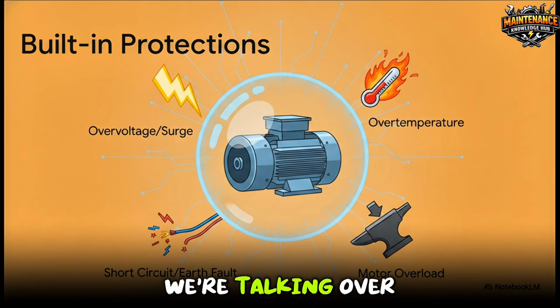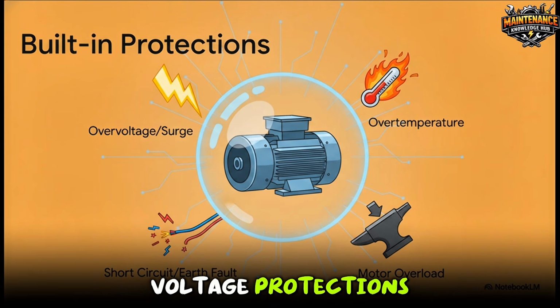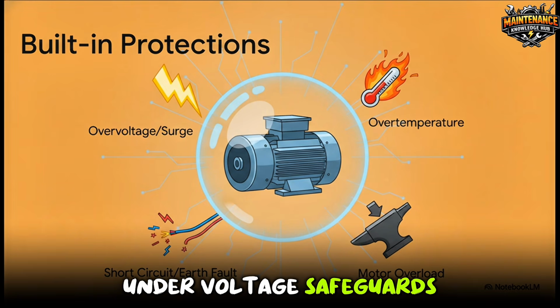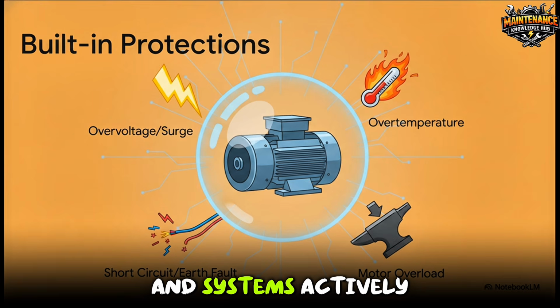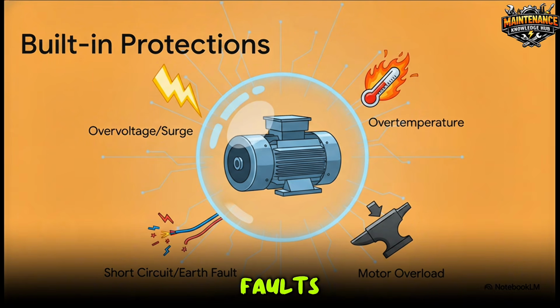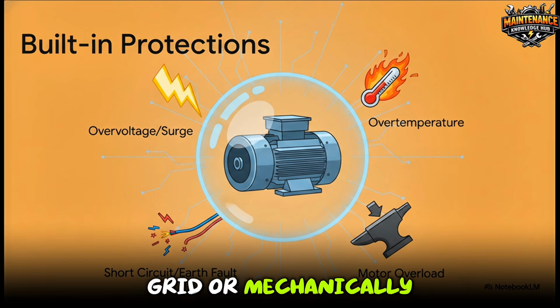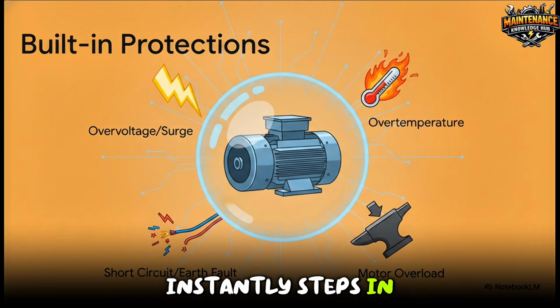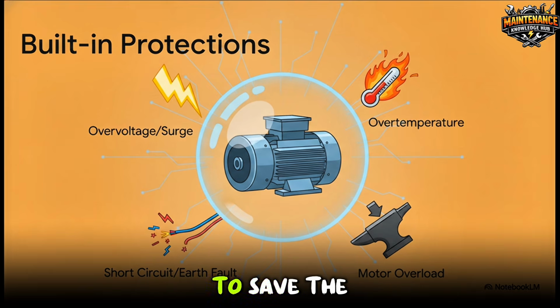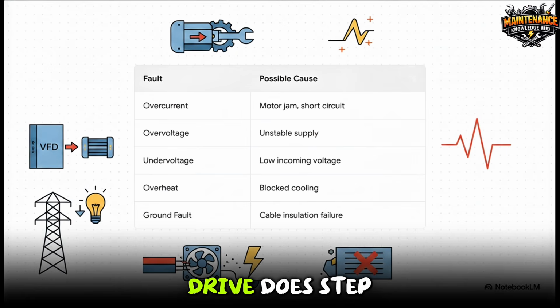runs. We're talking overcurrent and overvoltage protections, undervoltage safeguards, over-temperature monitors, and systems actively looking for earth faults, motor overloads, phase loss, and short circuits. Basically, if something goes wrong on the grid or mechanically, the VFD instantly steps in and safely shuts down the operation to save the equipment. And when the drive does step in to protect the system, it throws an error code.